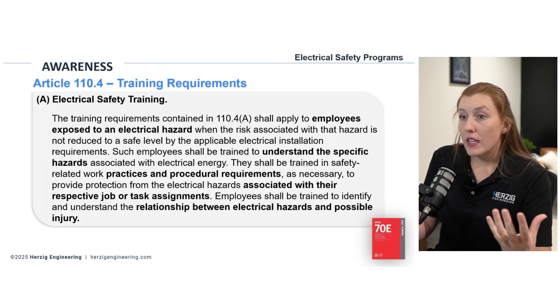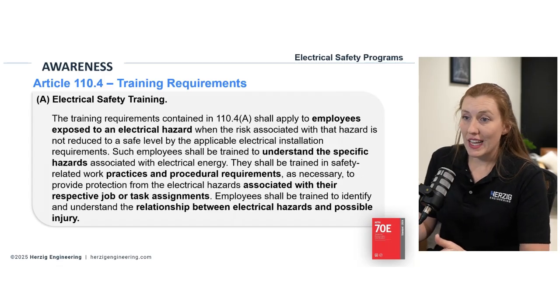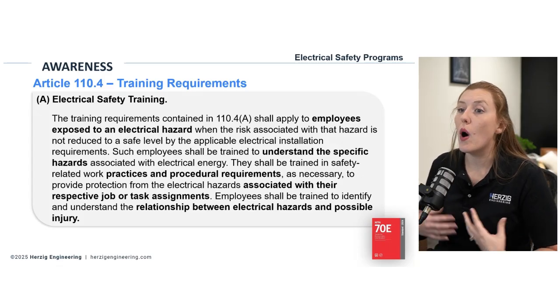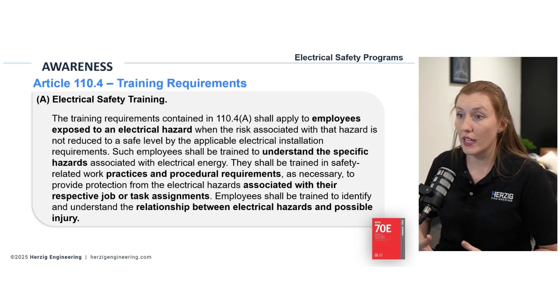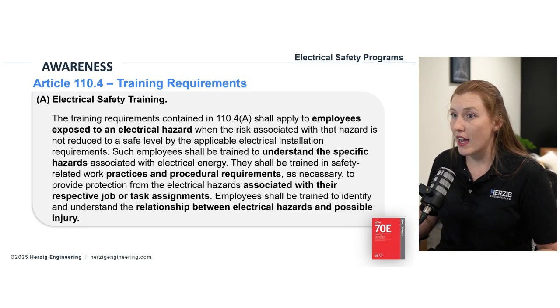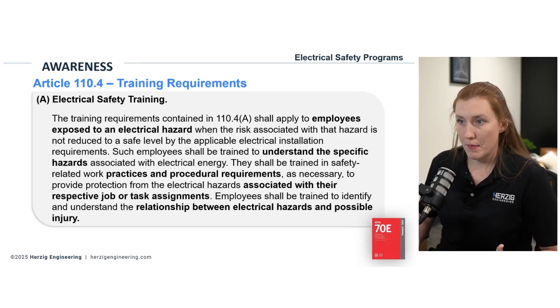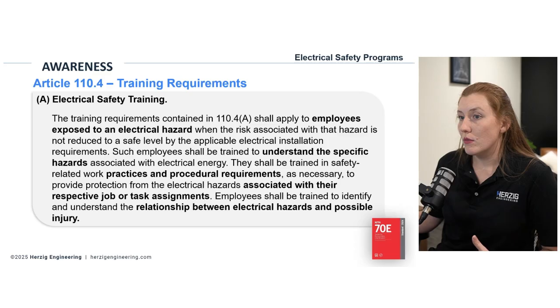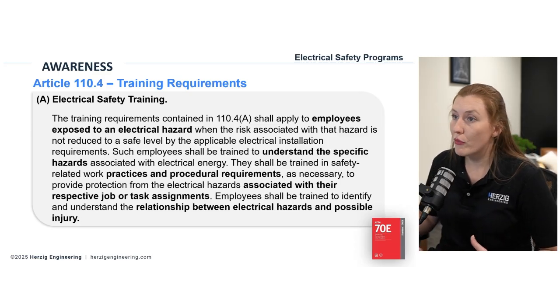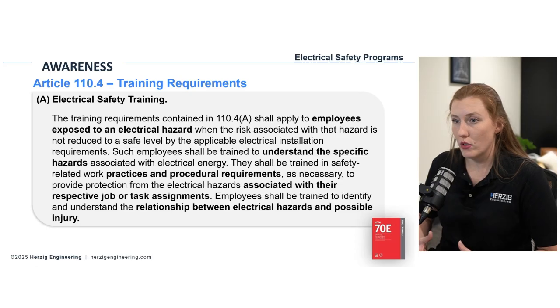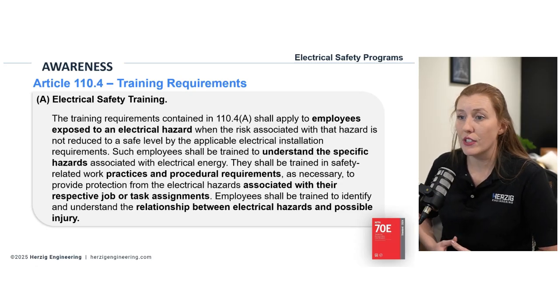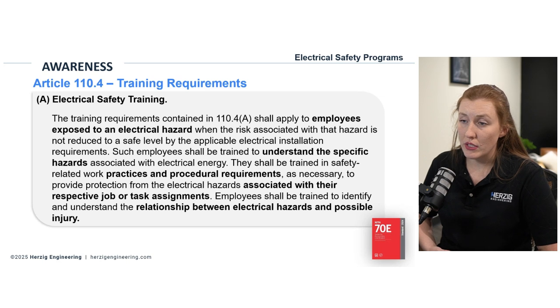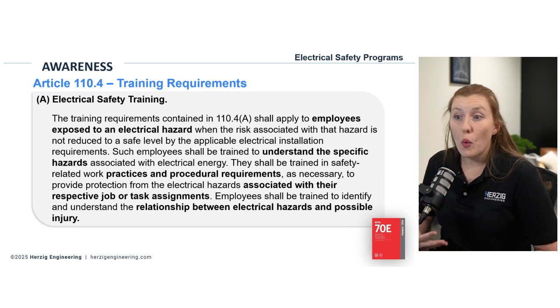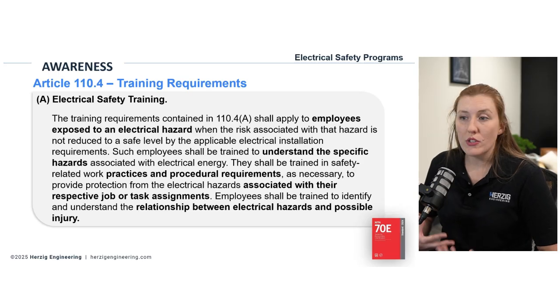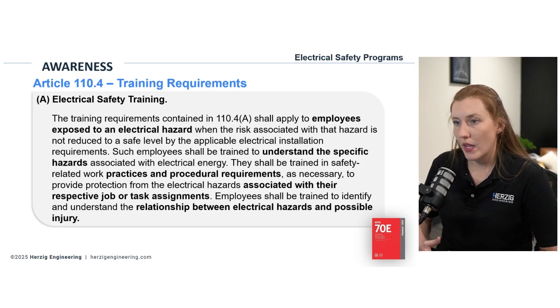For the 110.4 training requirements in NFPA 70E, this applies to all employees who are exposed to electrical hazards, any of them - shock, arc flash, arc blast, electrical fires, whatever it may be - especially if they're going to be in an area where that electrical work is performed. Again, they're potentially exposed to it. So you have to understand those specific hazards, what procedures and work practices you need to put into place, and any protective equipment associated with their respective jobs or tasks.